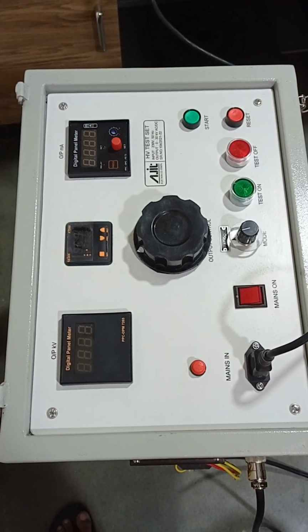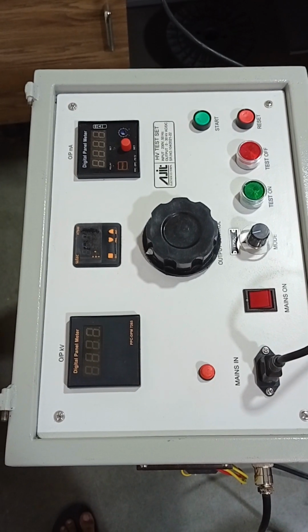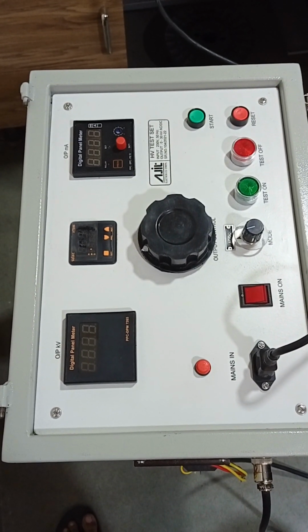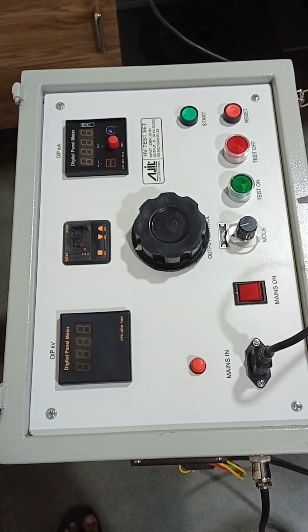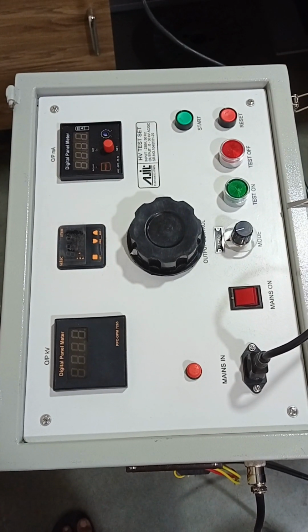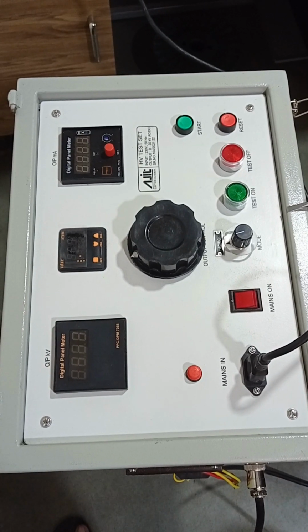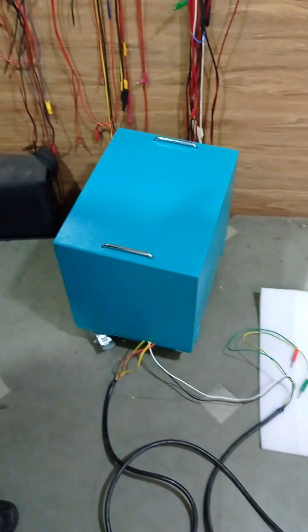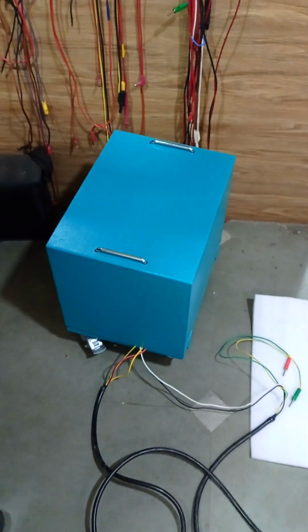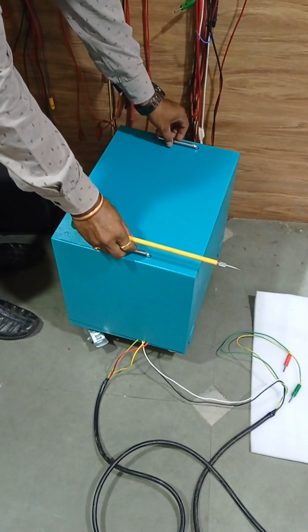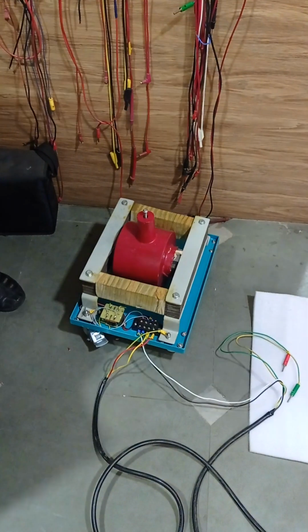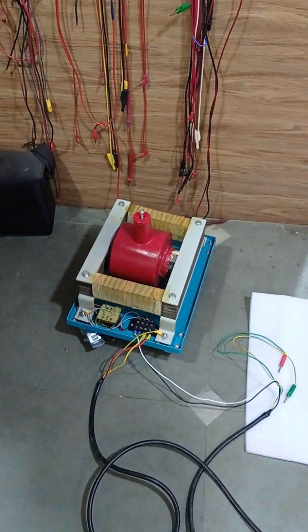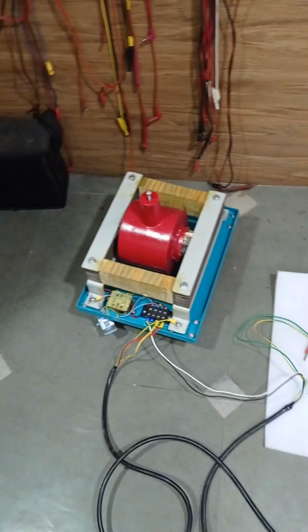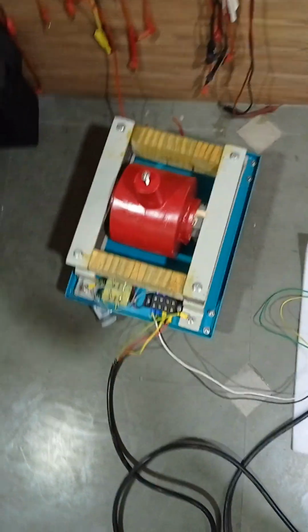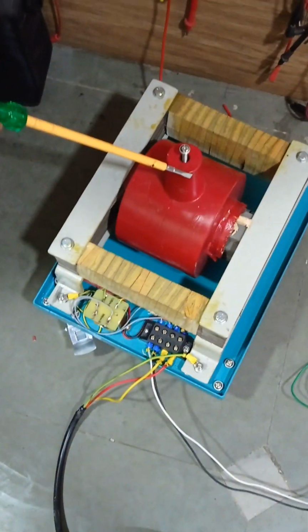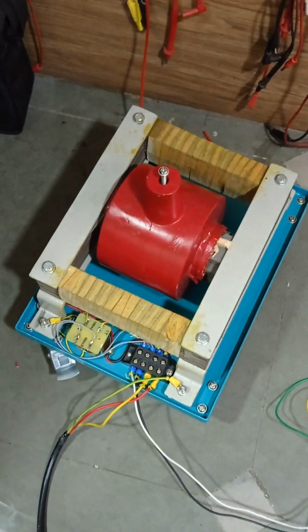This is a high voltage test set, AC as well as DC. Rather, this one is particularly a control unit for the combined AC and DC HV test set. This is the AC high voltage unit. We can simply remove this cover, and inside we have the high voltage transformer. These are all connections made. This one is the high voltage output terminal in AC.